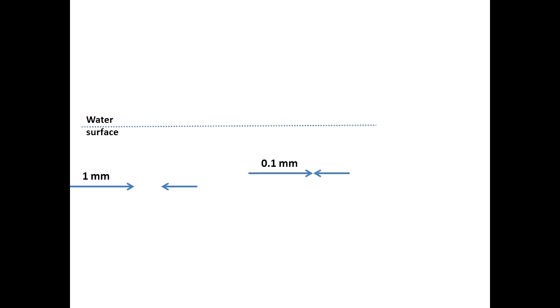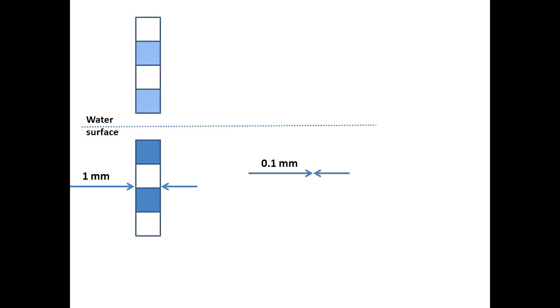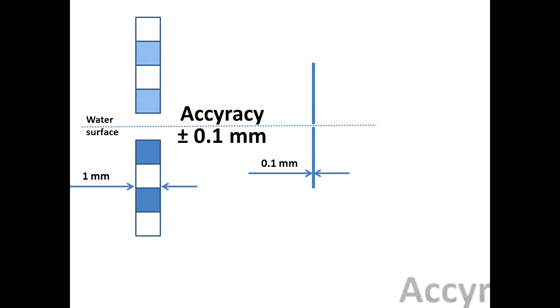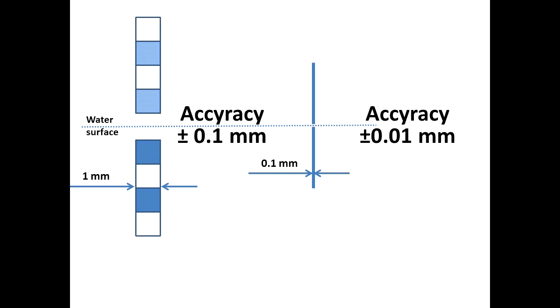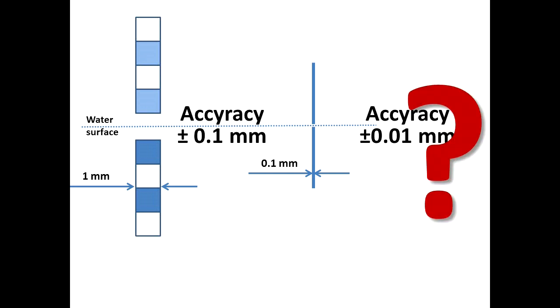It is logical to assume that if we reduce the thickness of the measuring tip by a factor of 10, it was, as you remember, 1 mm, and now it would be 0.1 mm, the accuracy of this tool should also improve by an order of magnitude. The only question is how reliably we can optically recognize the so-called calibration position with such small details of this device.